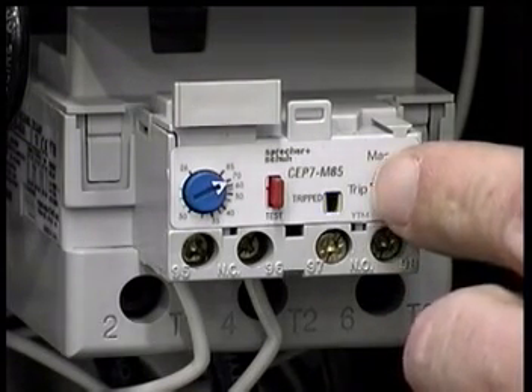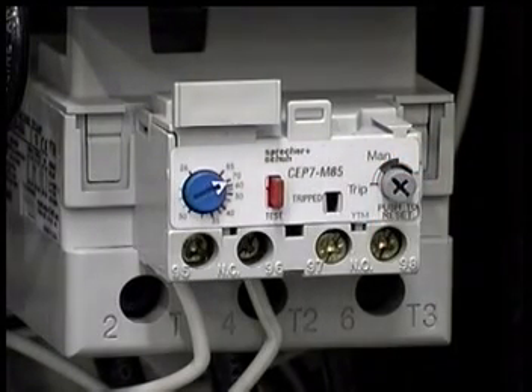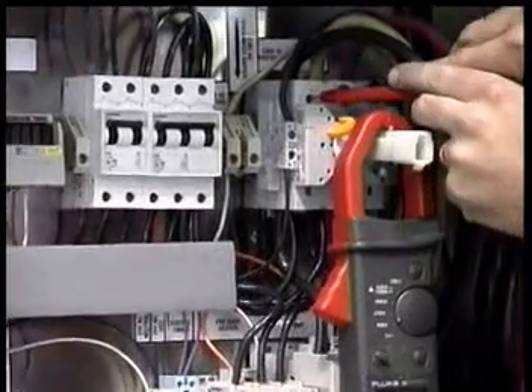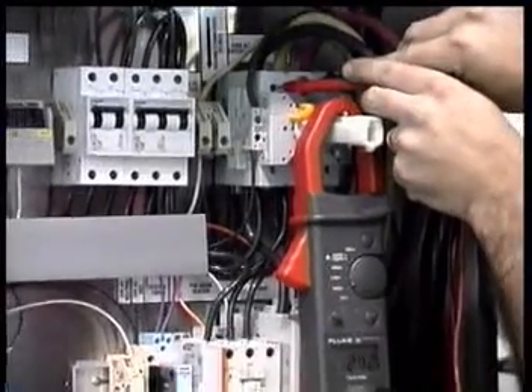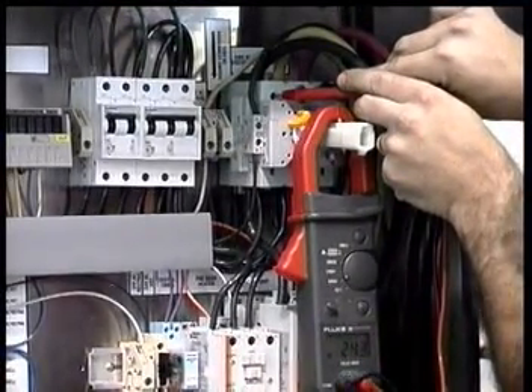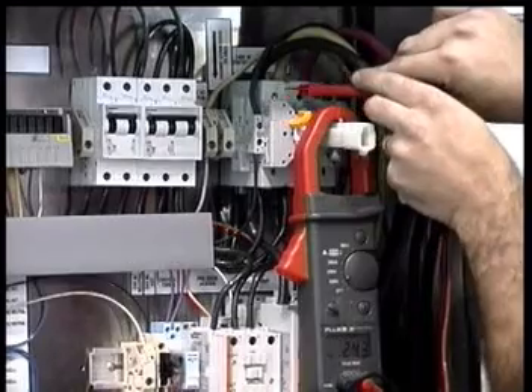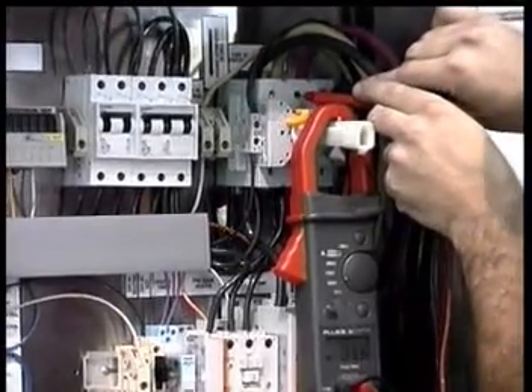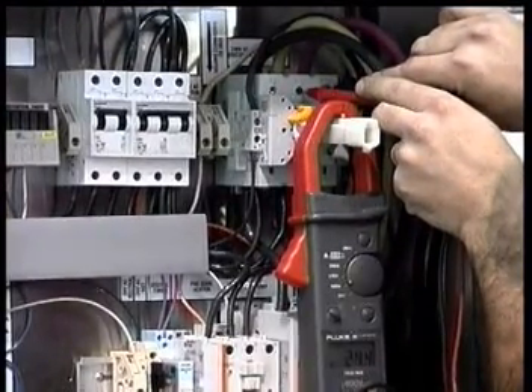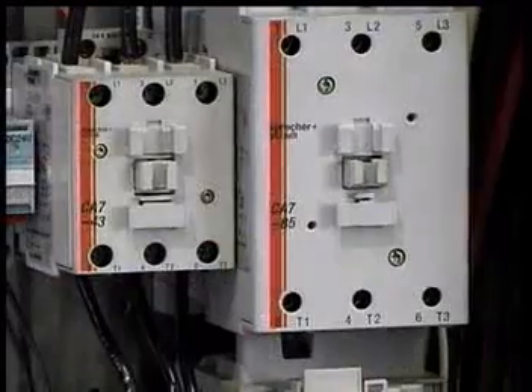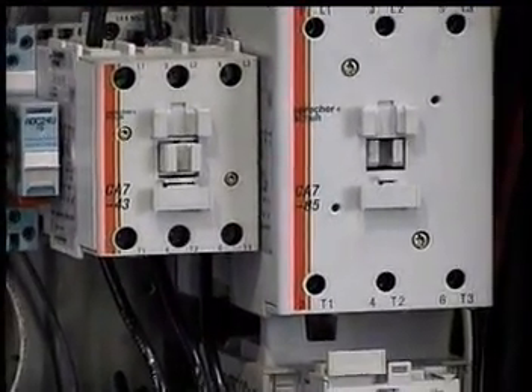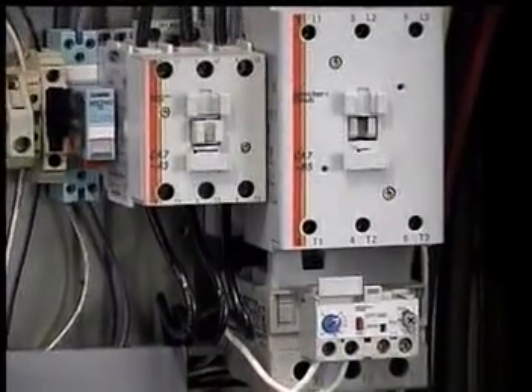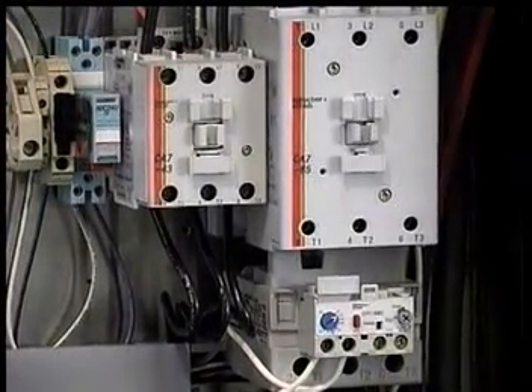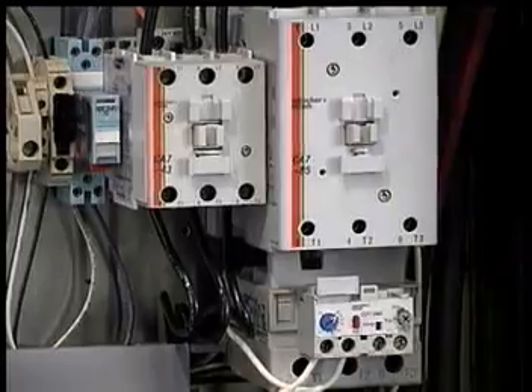Notice when the overload is tripped, a yellow flag is present in the tripped window. When it is reset, the flag is removed. The motor should run after the overload is reset. If the overload is not tripped, check for voltage at the top of the starter following previous instructions on checking for 220 volt power. Power must be present on all legs or the system will single phase and not run properly, if at all. If the overload is not tripped and the starter is pulling in but the motor is still not running, the contacts within the starter are faulty and the starter needs to be replaced.